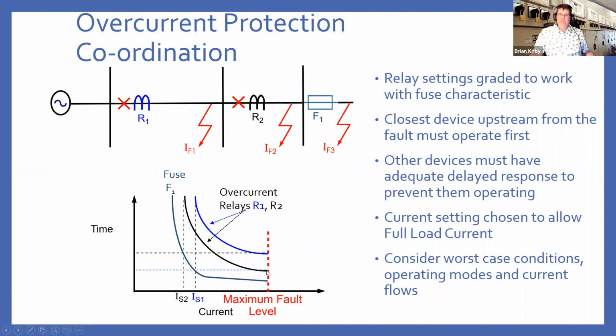And what you can do is set time delays. So typically you will coordinate your delay at the maximum fault level. So here we've decided what the delays between relay 2 and the fuse, and relay 1 and relay 2, are going to be. And we've set the characteristics to reach those points. And then when you plot those respective curves, you see that our set points are here and here. So our setting point 2 is the minimum current at which our relay will start to operate. And setting 1 is our minimum point at which relay 1 will start to operate. And that way we achieve time discrimination.